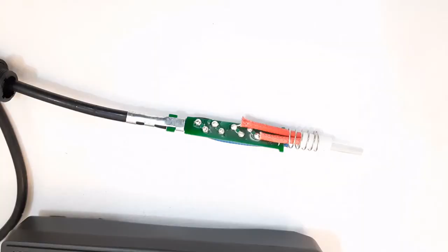We will check the resistance between these two red wires, which are of the heating element. The resistance is close to infinity, more than 20 mega ohm, which is a clear indication that the heating element has gone bad.